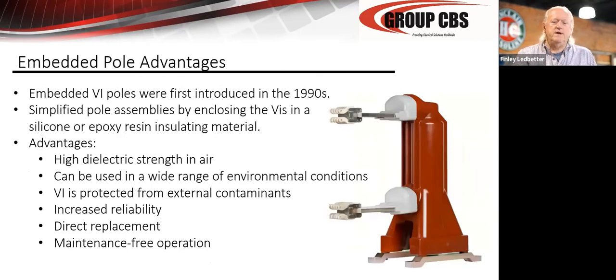Newer breakers have embedded poles, poles that are not assembled. The vacuum interrupter is encased in epoxy, for instance. Those are very stable. That's a very good technology. Those poles are available for a lot of breakers that had assembled poles on them. They have a high dielectric strength and a lot of overload capability. Spider webs, bugs, and moisture can't get to them. It's a really good idea, if you're going to be specifying new vacuum breakers, to make sure they're embedded type poles and not an assembled type pole. It's a big difference in overall longevity and performance.